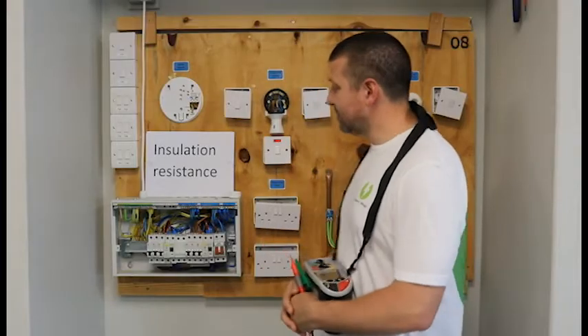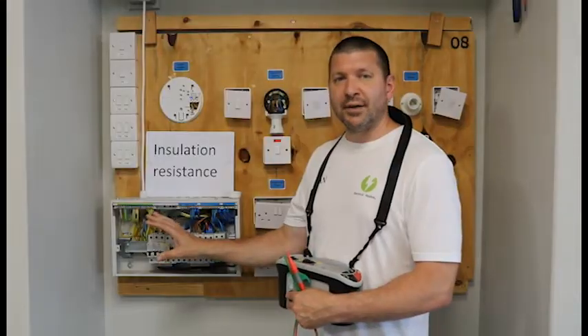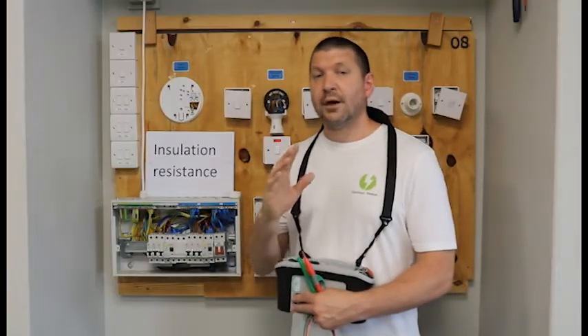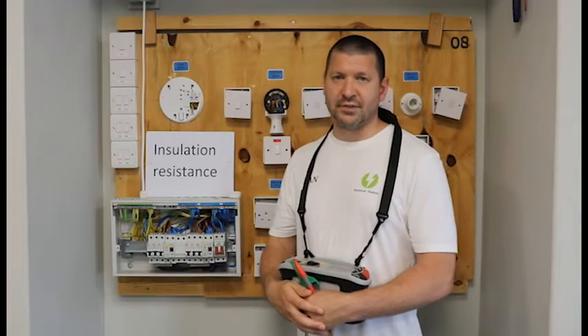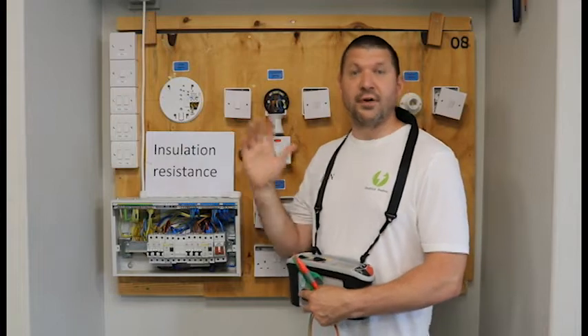For the insulation resistance test, we don't move any cables within our DB and we don't remove or move any cables within our circuit — it is just ready to go. More importantly, there are pre-test checks we have to do before we do an insulation resistance test.